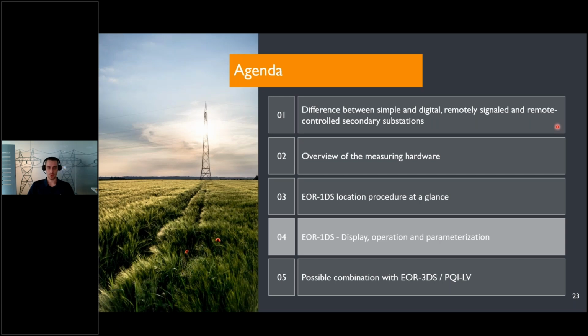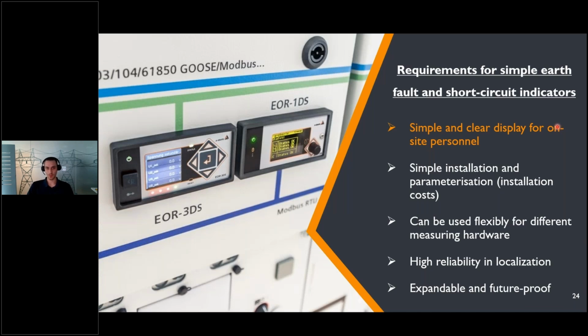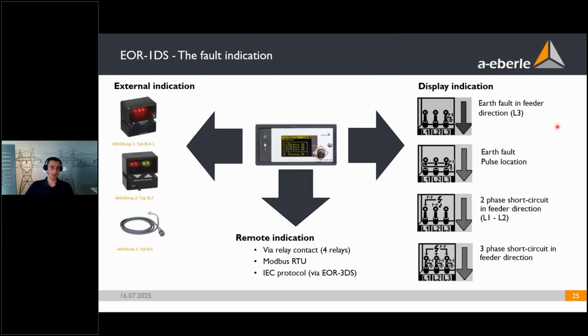So then let's get into the EOR-1DS display, operation, and parameterization. Again, one of the features that was mentioned would be that the EOR-1DS, as an earth fault and short circuit indicator, should have a simple and clear display for on-site personnel. The indication on the EOR-1DS has three main paths. One is the external indication. So you can connect a blinking light of two different types to your device, and you can install the blinking light outside your station, and that way your technician would only need to drive from station to station and not enter the station in order to precisely detect the fault location.